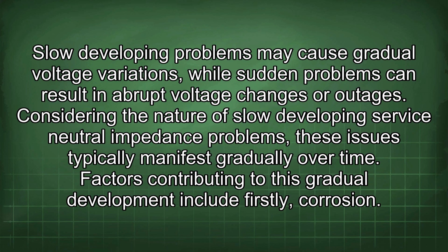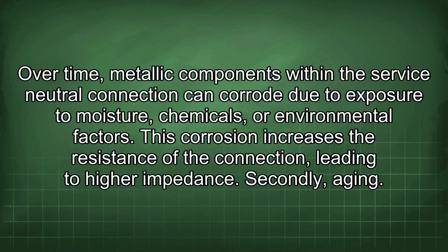Considering the nature of slow-developing service-neutral impedance problems, these issues typically manifest gradually over time. Factors contributing to this gradual development include, firstly, corrosion. Over time, metallic components within the service-neutral connection can corrode due to exposure to moisture, chemicals, or environmental factors. This corrosion increases the resistance of the connection, leading to higher impedance.